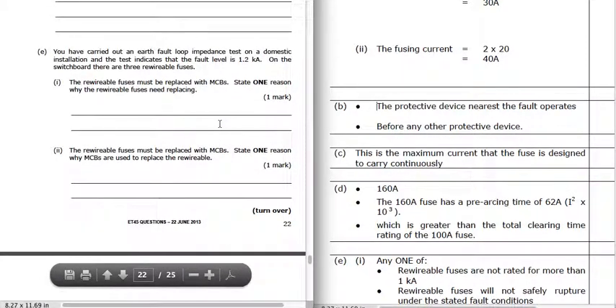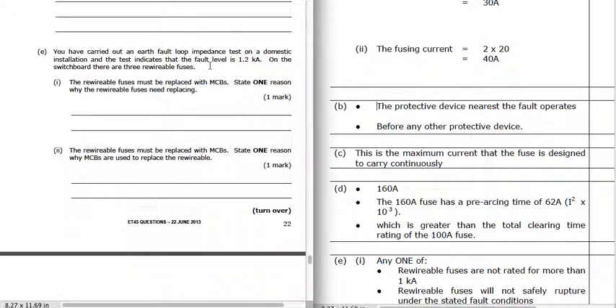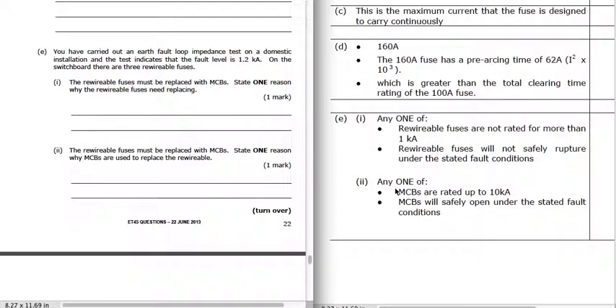An earth fault loop impedance test on a domestic installation showed a fault level of 1.2 kiloamps. On the switchboard there are three rewireable fuses, which are only rated for 1 kiloamp — so they won't safely rupture under the stated fault conditions. It could cause an arc and a sustained current — they might not be able to break that current. The rewireable fuses must be replaced with MCBs, because MCBs are rated up to 10 kiloamps and will easily be able to interrupt 1.2 kA.